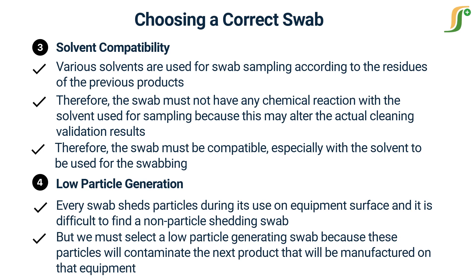All the above features should be considered before selecting the swab for cleaning validation sampling. You may add more things to this list, like the size of the swab. The swab must be sufficient in size to cover the sampling area by 5 to 10 swabbings. A bigger swab will be able to hold more material from the sampling surface. A swab plays an important role in successful cleaning validation.